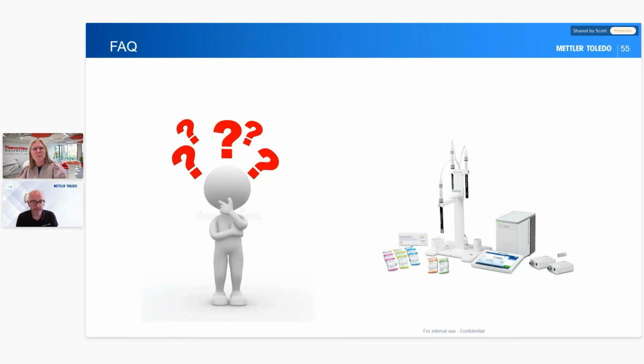No, not really, other than the recommended range. On the Mettler ones, we have a temperature range, which is the temperature range it will measure between, and it's normally between 10 degrees and 90 degrees, somewhere like that. So, for example, you'd struggle to use it outside in the Arctic or Antarctic. And obviously you need to keep the electrode warm before you take measurements in ice and very cold solutions. But generally, if you keep it at room temperature when you're not using it, that's the best thing.